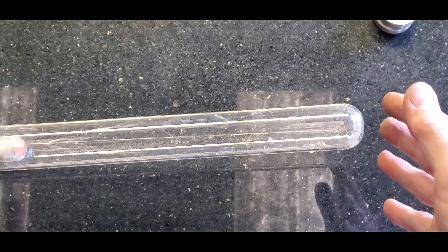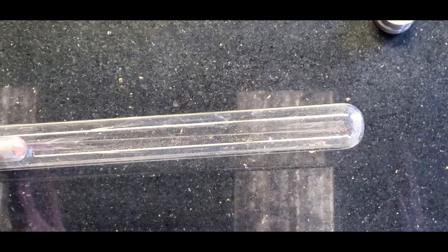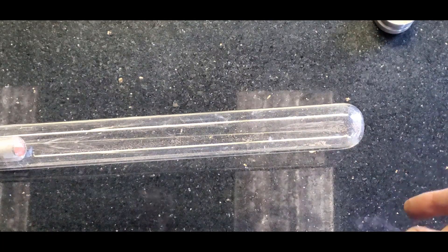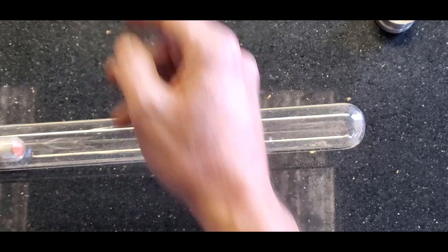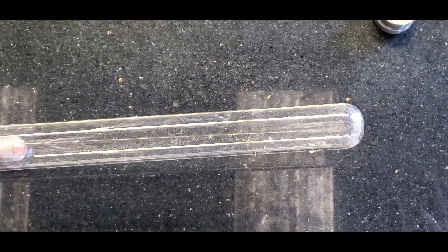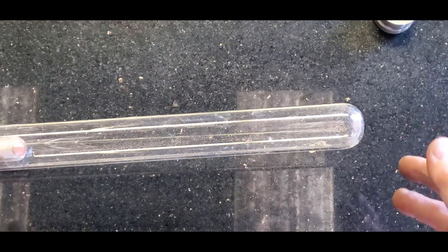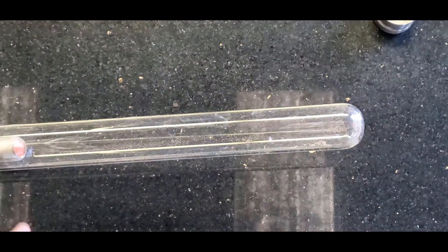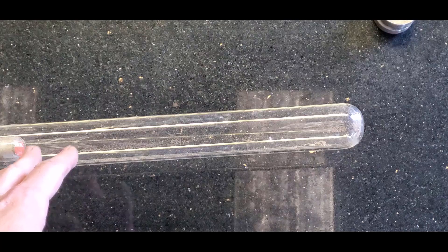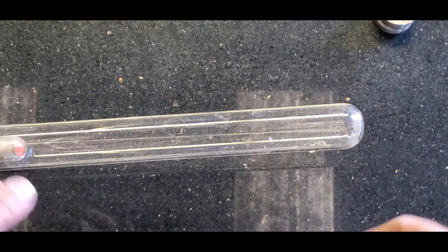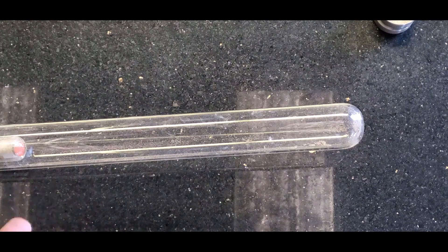These tubes are arranged in a bank of maybe 36 tubes in a rectangle and they're down vertically in the wastewater channel, and the water is flowing across and around the tubes. If your channel is two feet wide and you have a two foot wide module of 36 lights, there is nowhere that the water can go and the bacteria can go without getting exposed to the ultraviolet radiation, and that basically shreds their DNA and they become inactive. It doesn't remove them from the water but they can't reproduce so they're dead.